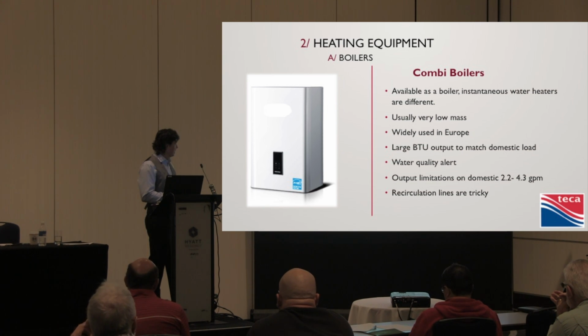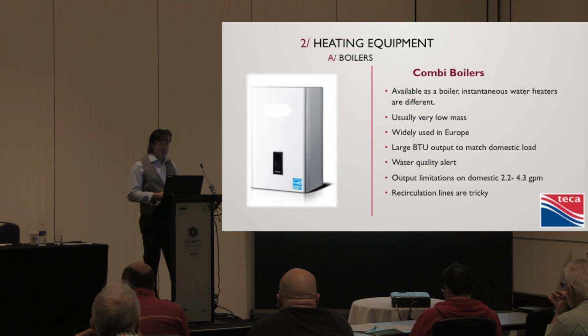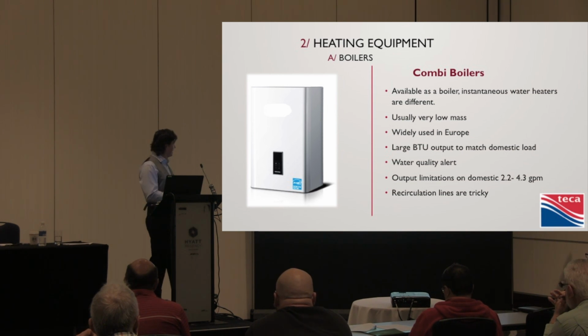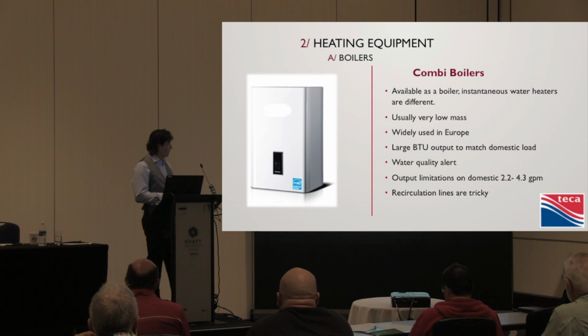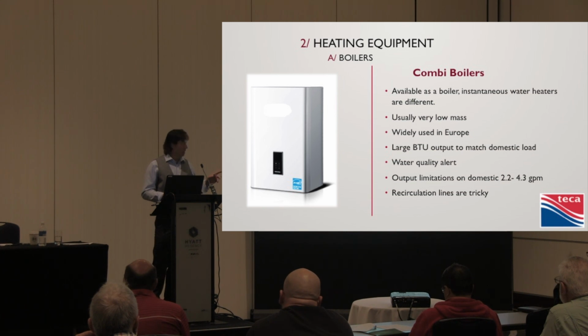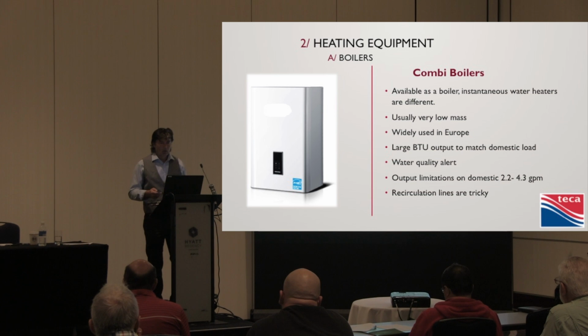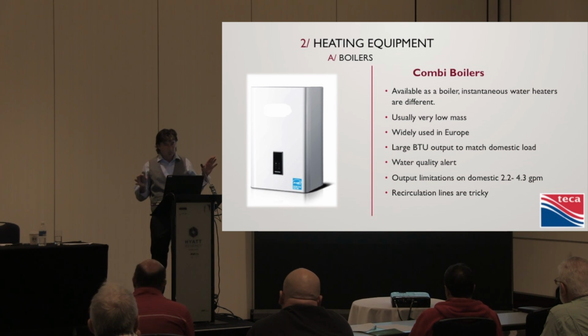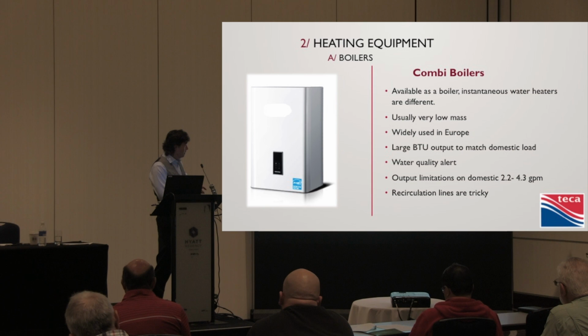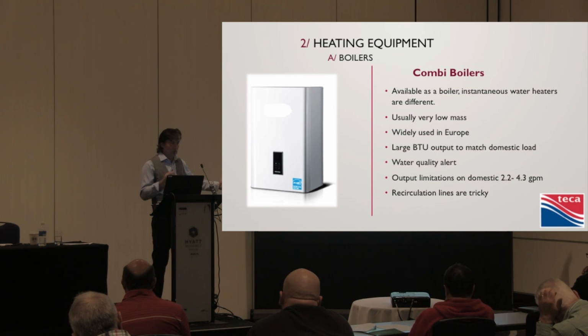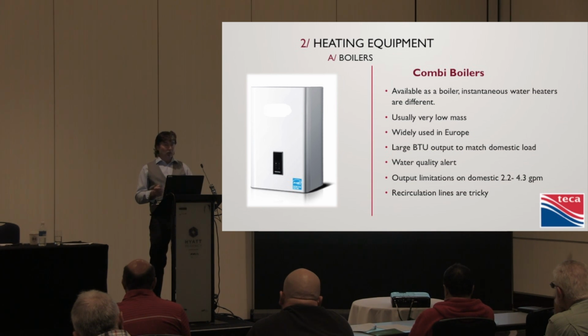Europe's chock full of these things. They think we're in the Stone Age with our storage water heaters. I had a guy stop by my office from Ireland, and he was just shaking his head. Anyways, they have a large BTU output, so no longer are we sizing these things to the heating load. If my boiler is doing space heating, it can also do domestic heating through storage. But when we're heating water instantaneously, which is what we're saying we're doing with this one, part of it's doing the house load. So let's go back to the heat load of that house, 53,000 BTUs, let's say. So that boiler is going to be 150 to 230,000 BTUs.